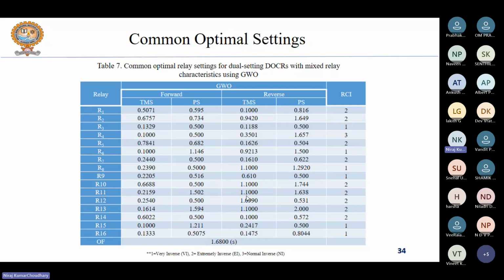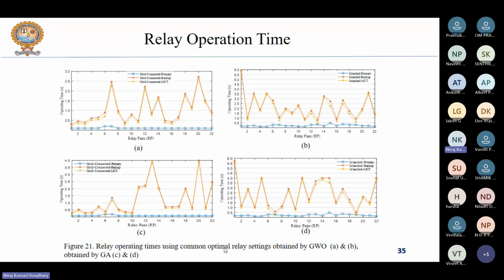So the proposed solution, as we have seen in the flow chart and diagrams, is that you need to calculate the common optimal relay settings, again by considering the different modes of operation of the microgrid. So here we have calculated the relay settings, that is TMS, PS, and the optimal selection of the relay characteristics, and based upon that, the total time of operation of the relays calculated is 1.68 second, right? And these are the relay operating times of your relays by using these two types of optimization algorithms, that is your gray wolf optimization as well as your genetic algorithm optimization.